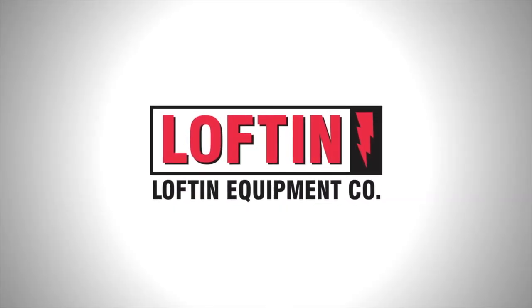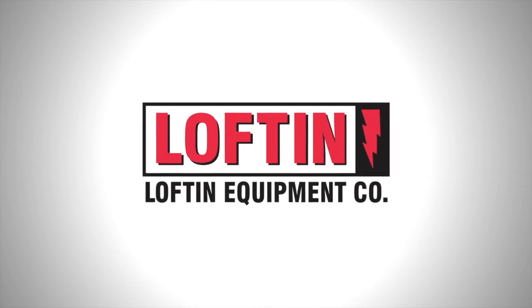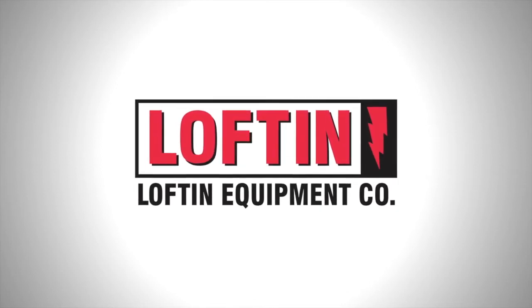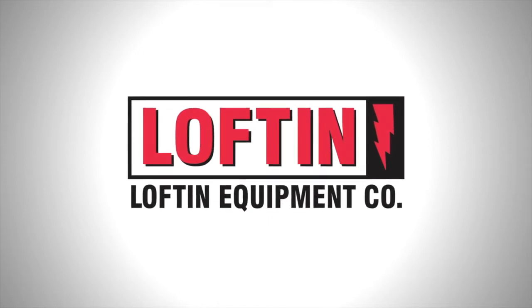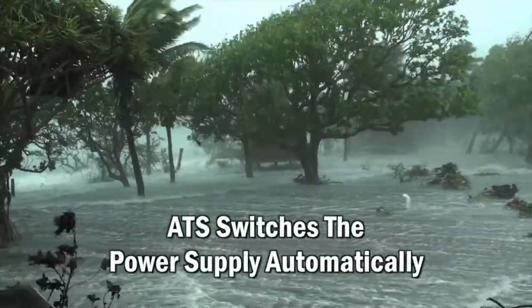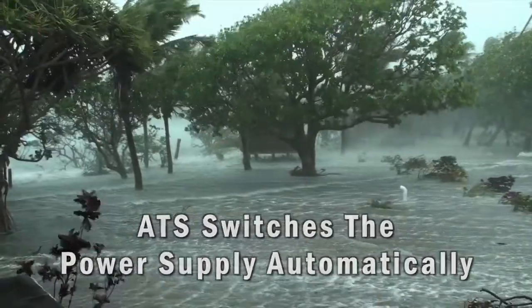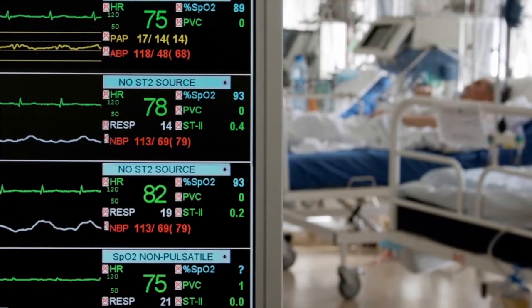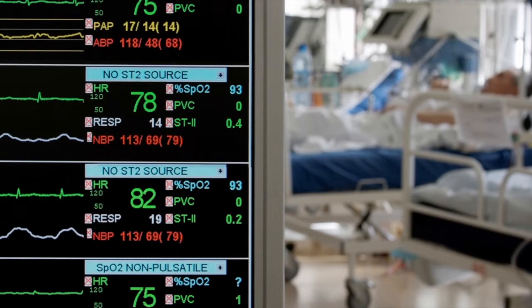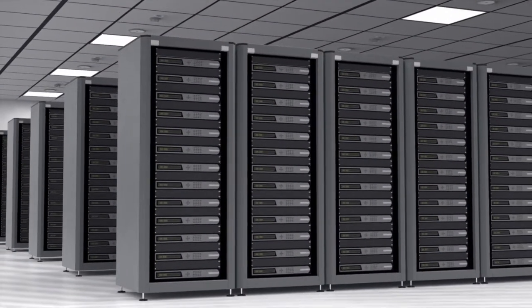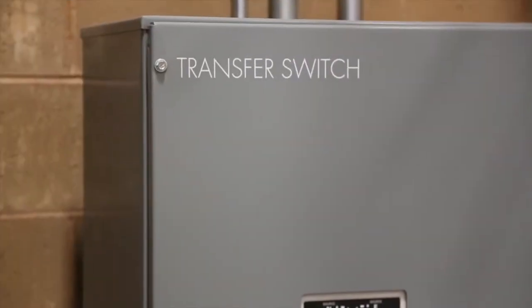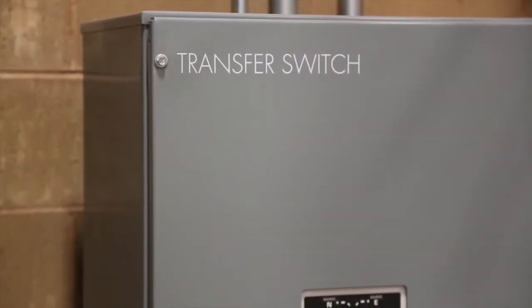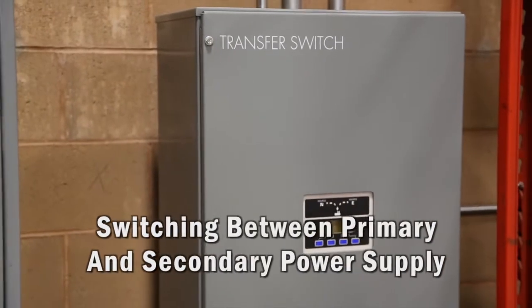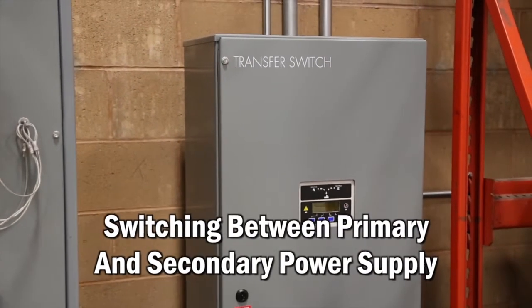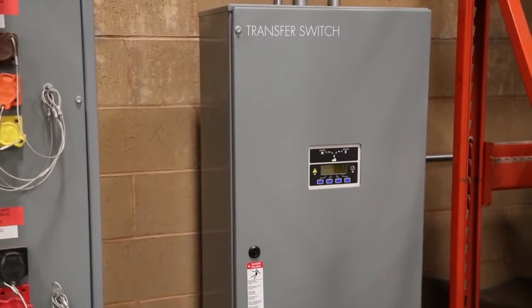Most standby generator set systems are arranged to start automatically when the utility or primary power to the system load is interrupted. Interruption can be caused by numerous reasons, such as weather or equipment failure. Many standby systems are there to provide backup power to critical life and/or economic load, such as hospitals and telecommunication stations. Typically, an automatic transfer switch, most frequently called an ATS, is used to transfer the load between the primary power source and the standby generator set.